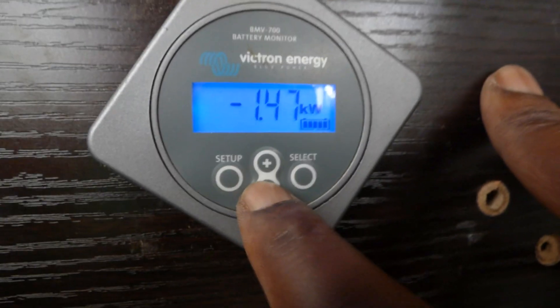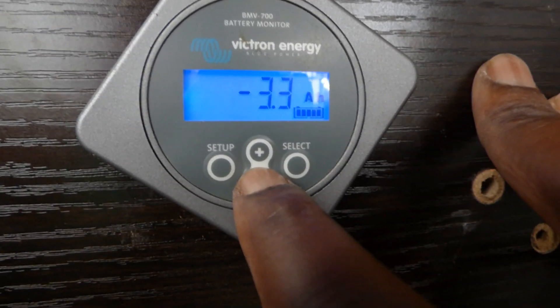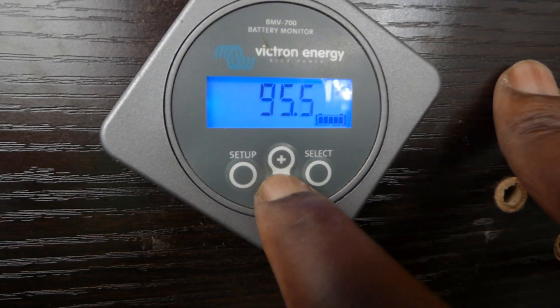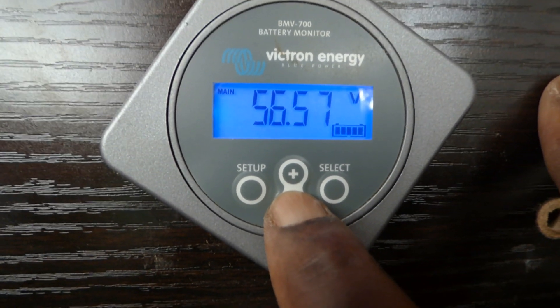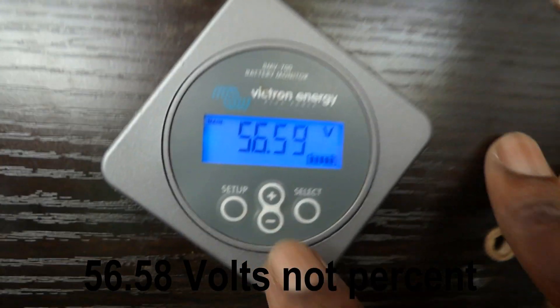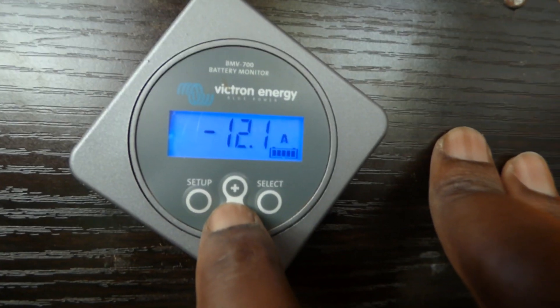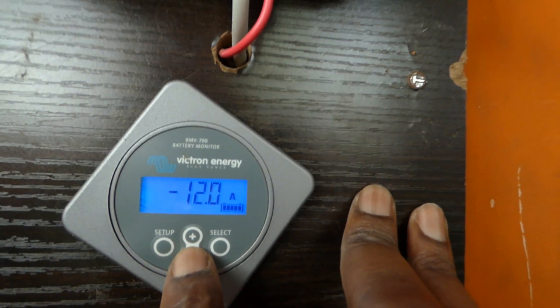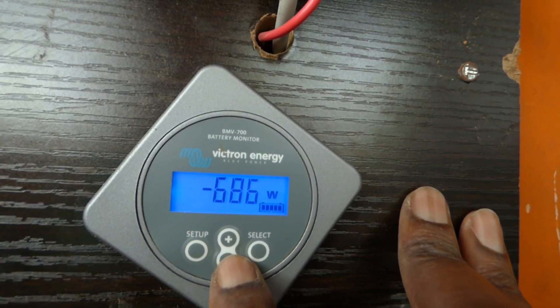I'm pulling 1.48 kilowatts out of my battery — so it's about 1400 watts. We're using 2200 watts total, so our PV is short. Batteries are at 95 percent — 56.58 volts, not percent. So you can see it's bouncing. This is the advantage of a lithium-ion battery: you can pull high current out of it. We're currently only pulling 12 amps, which is nothing, and the battery voltage doesn't sag. Now it's dropped to 687 watts being pulled from the battery — before we were pulling 1.2 kilowatts. The sun just came back up.